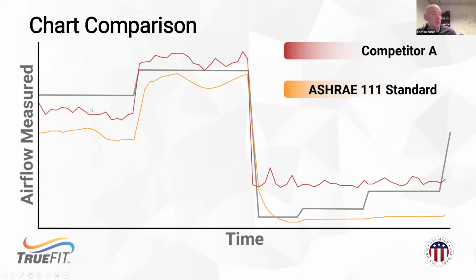The interesting thing here is when we close that damper down, we see competitor A get a false floor. This is about 6,000 CFM on a 22,000 CFM air handler. So that's a pretty significant offset that they had. And we see even as we step that damper back open, those air velocities are low enough where they're not going to register any new measurement there.